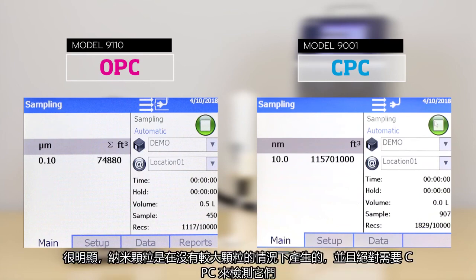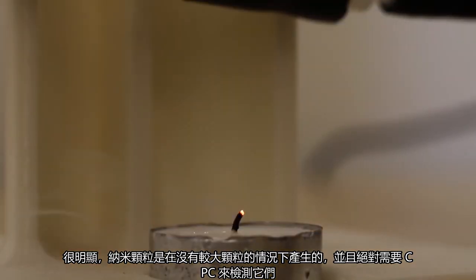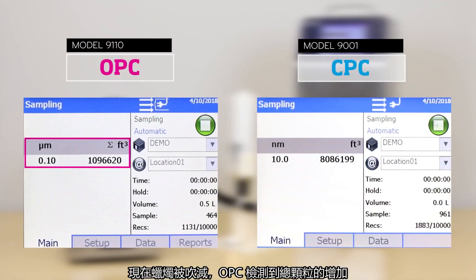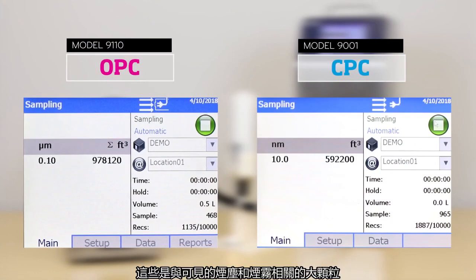It's clear to see that nanoparticles are generated in the absence of larger particles, and that a CPC is absolutely required to detect them. Now the candle is blown out, and the OPC detects an increase in total particles. These are large particles associated with visible soot and smoke. After a short time, both instruments return to baseline.